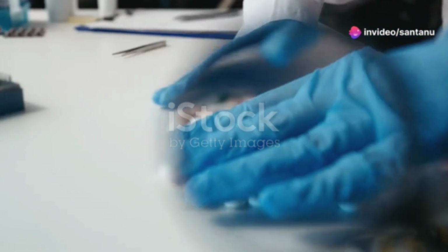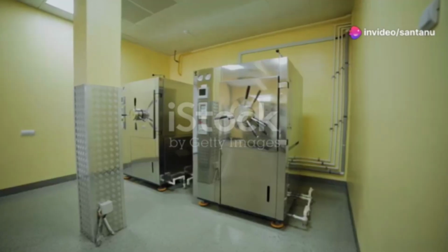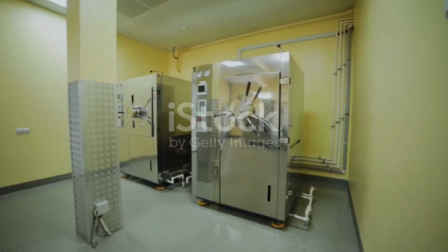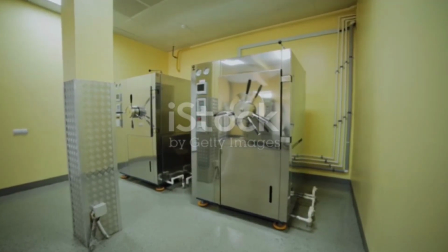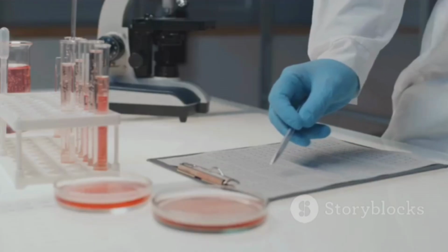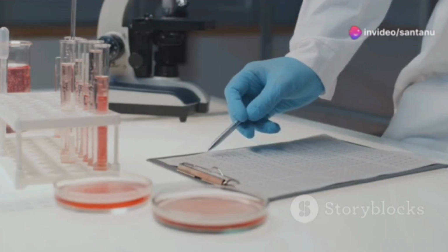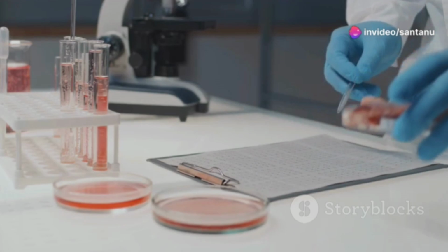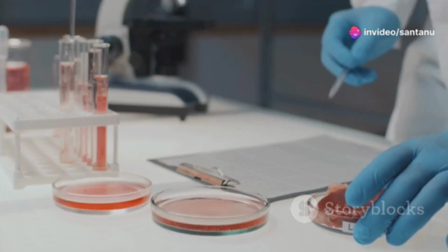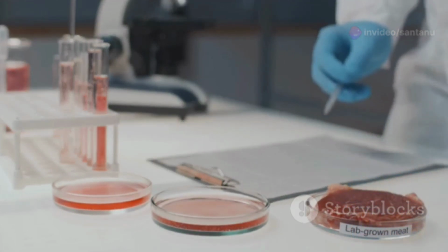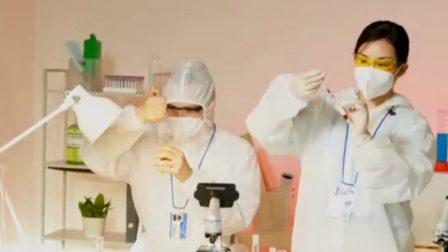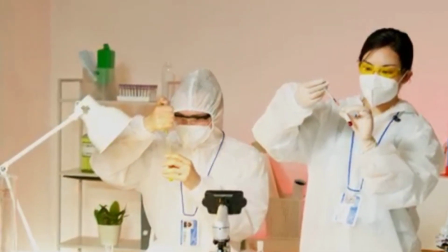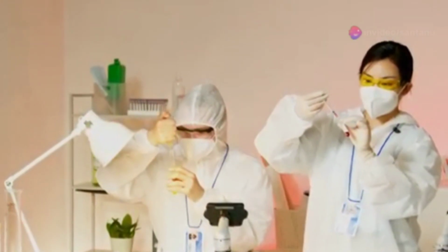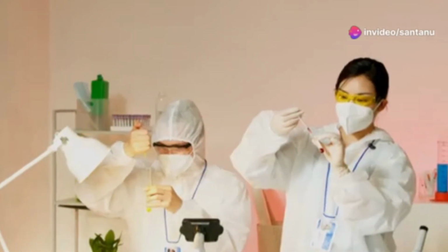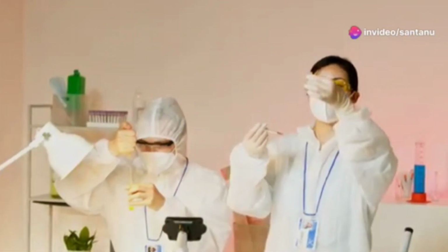Section 7. The role of validation in achieving 6-log reduction. Achieving 6-log reduction isn't simply a matter of subjecting products to a sterilization process and hoping for the best. It requires rigorous validation, a systematic and documented approach to demonstrating that the chosen method consistently delivers the desired level of microbial reduction. Pharmaceutical manufacturers must validate their sterilization processes using scientific principles, engineering controls, and statistical analysis.